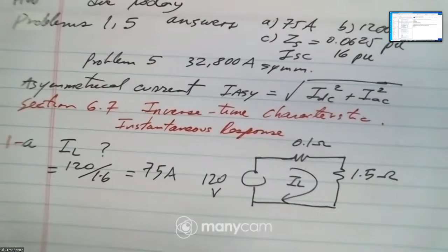So this is very simple. Then B, calculate the short circuit current. So if a short circuit current occurs here, let's put a switch here. So if the short circuit current occurs there, then B short circuit current equals 120 over 0.1. So that's 1200 amps.